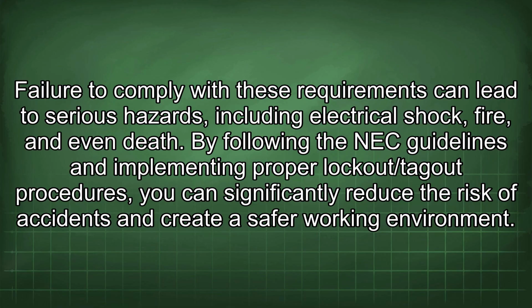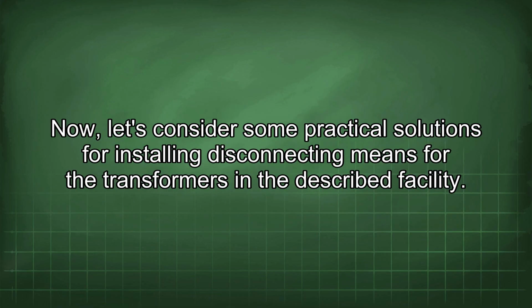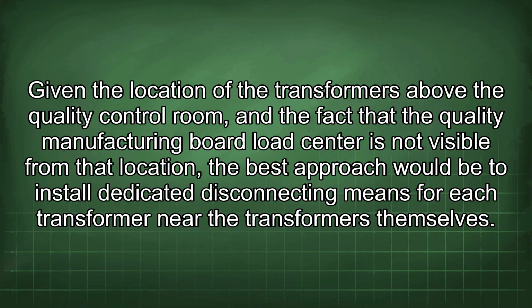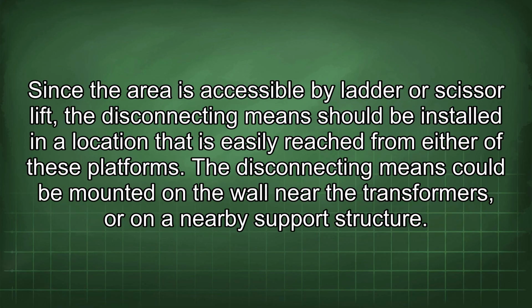Now, let's consider some practical solutions for installing disconnecting means for the transformers in the described facility. Given the location of the transformers above the quality control room, and the fact that the Quality Manufacturing Board load center is not visible from that location, the best approach would be to install dedicated disconnecting means for each transformer near the transformers themselves. Since the area is accessible by ladder or scissor lift, the disconnecting means should be installed in a location that is easily reached from either of these platforms.